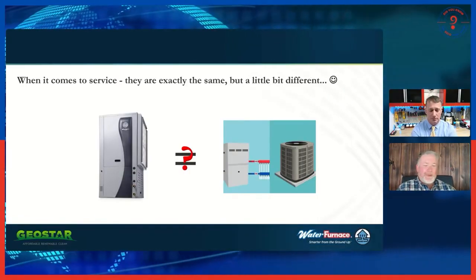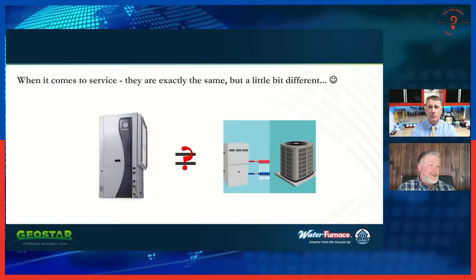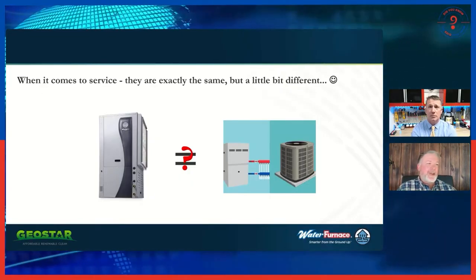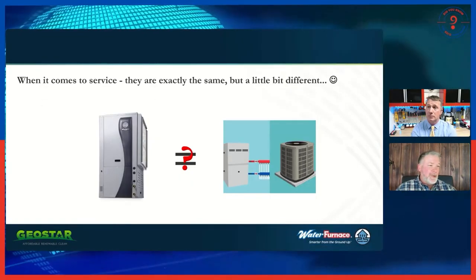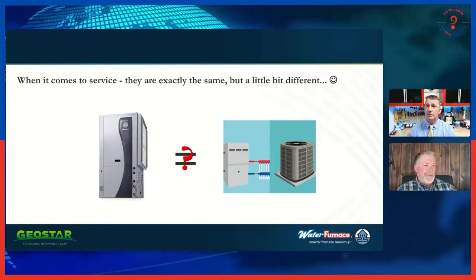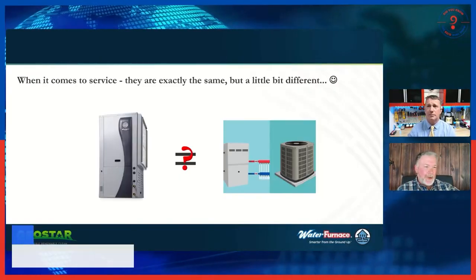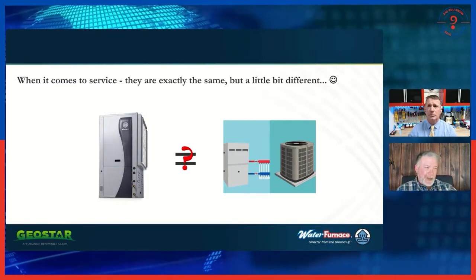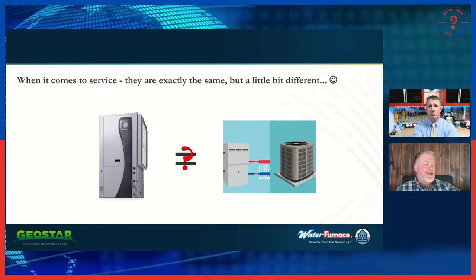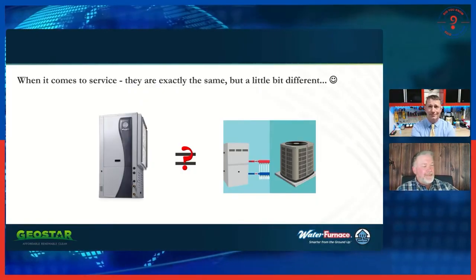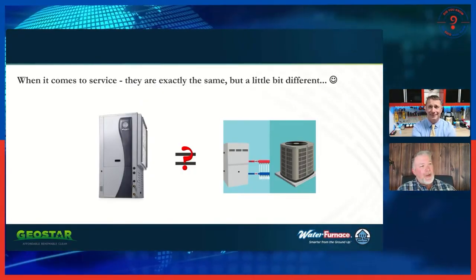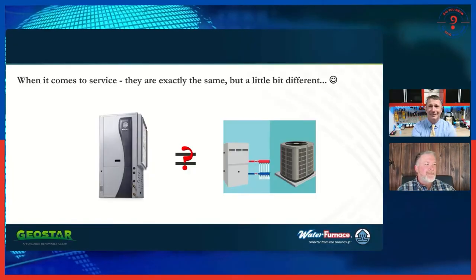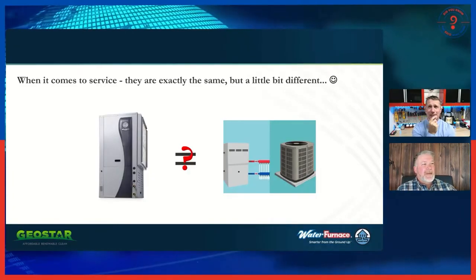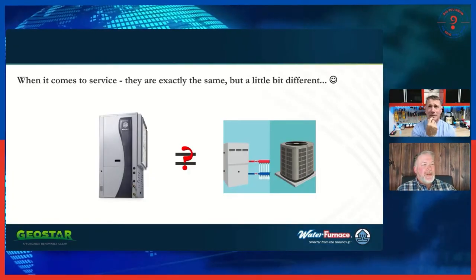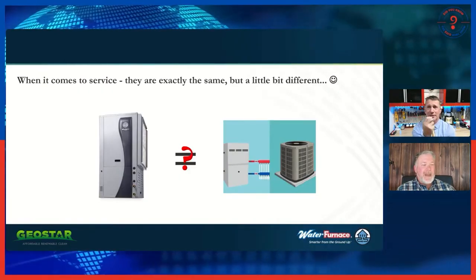And we have a couple methods. Obviously, the touch and feel method is a good place to start, but we also have waterside diagnostics. So just like you would do a BTU calculation, delta T times CFM times 1.08, we have the same thing on the water side, and it's delta T times GPM times the fluid factor. So it's the same formula, just a little bit different numbers. Instead of having airflow, we've got water flow. Yeah. So really the same. Oh, nice. Yeah, it's a great perspective to think about. Because that's all we're doing is talking about the amount of heat that's being transferred based on velocity.